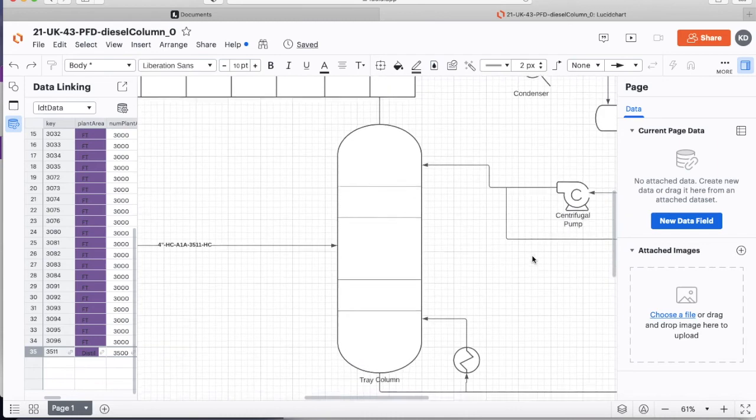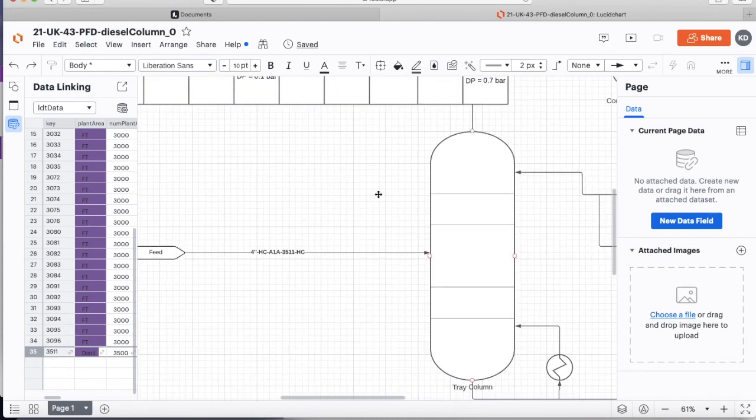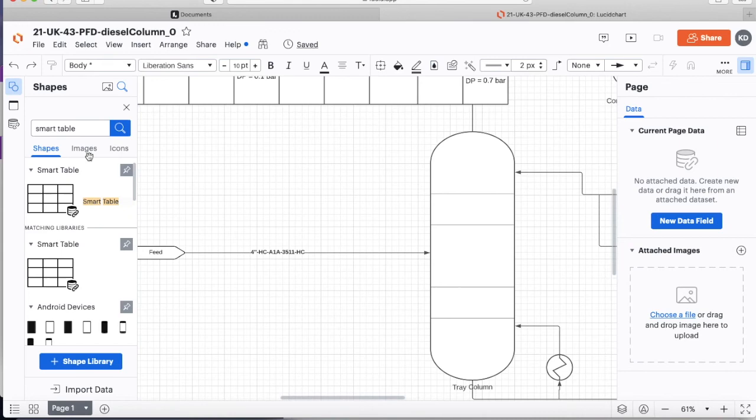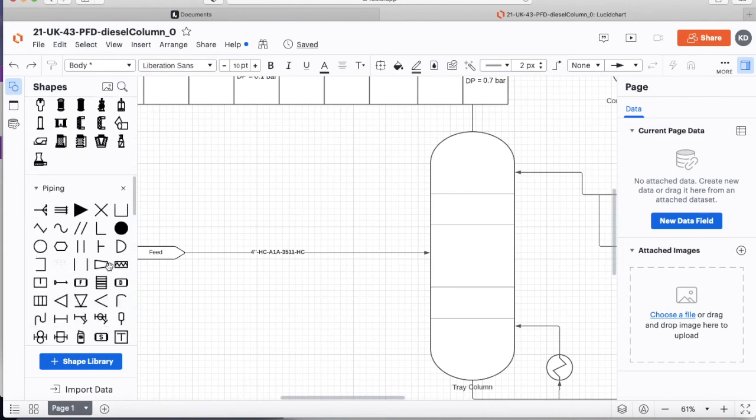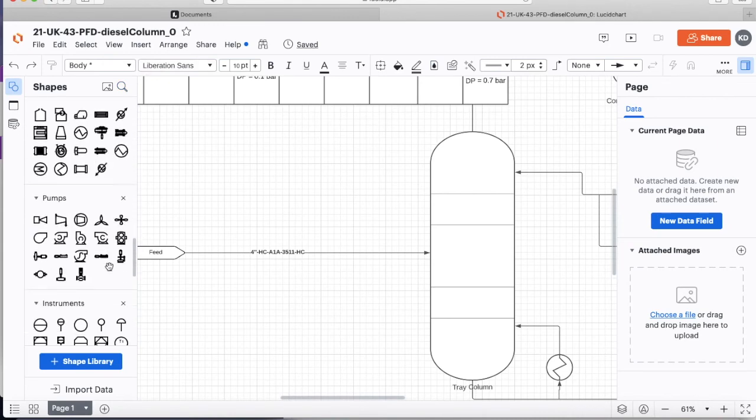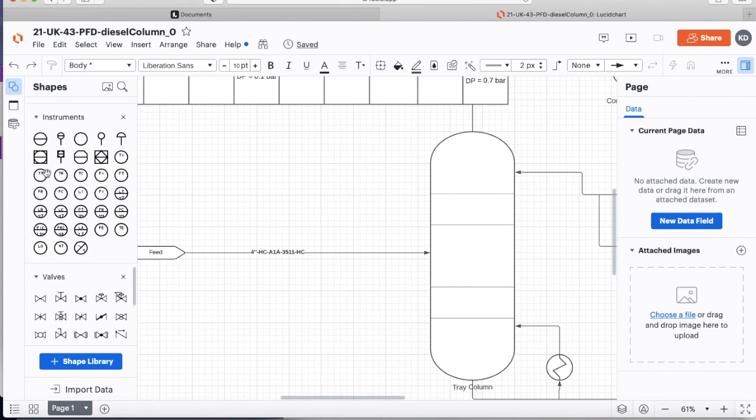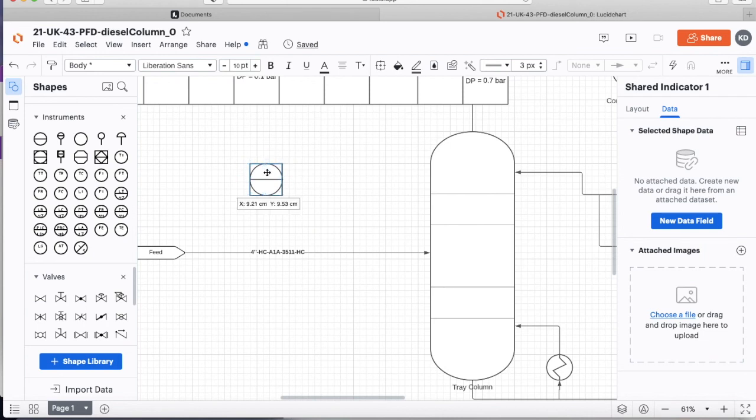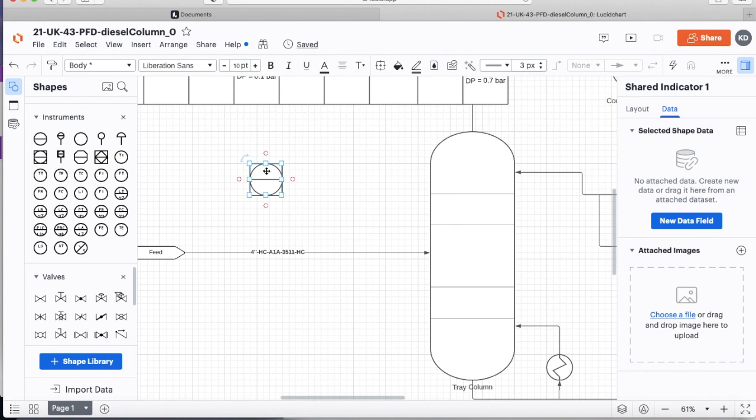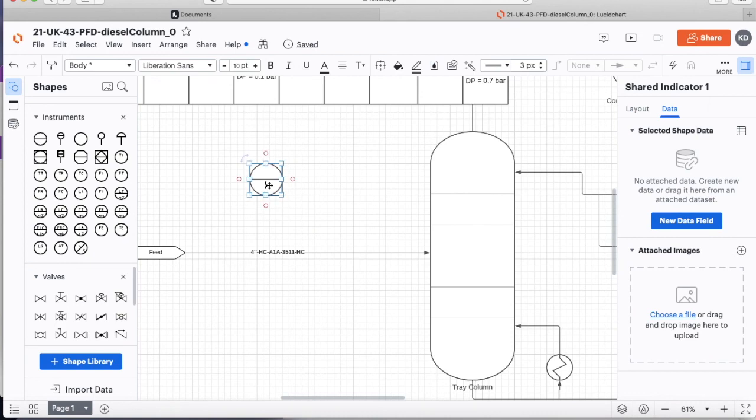And we can do that exact same trick with a bunch of other symbols within our P&ID, such as we could have instrumentation. We can attach instrumentation or we can attach this particular instrumentation to some data. And we can tell it to fill in something in the top of this instrument tag. And we can fill in something in the bottom of this instrument tag. This might be the prefix like FIT. And the bottom might be the actual tag number. So it's in the top, FIT. And in the bottom, one, two, three, four.